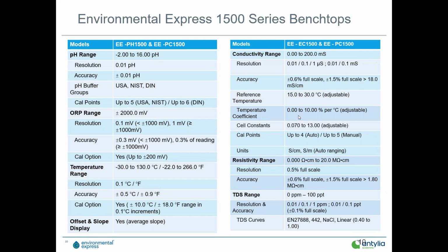Reference temperature is adjustable. A temperature coefficient, the default on this is normally 2% per degree. That is adjustable. Obviously, your cell constants, a 0.1, a 1, and a 10. That'll cover all electrical conductance ranges out there, up to 4 cal points. Now, auto cal, so this instrument is pre-programmed with 4 conductivity standards: 84 microsiemen, 1413, 12.88 millisiemen, and 111.8 millisiemen as well for the high end. Then you can do up to 5 manually.